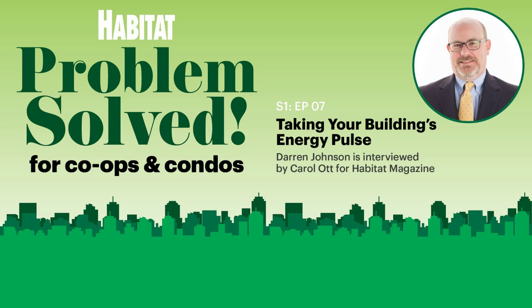If you think about large buildings, you're going to have mechanical ventilation. You may have a cooling tower, a chiller, multiple boilers, much larger pumps and motors. You could have a cogeneration system or a separate domestic hot water system. A BMS is not going to be tied into all of that equipment and all of those systems. It's going to be very specific. What real-time energy management does is leverage that BMS system and then expand upon it. You're creating a bigger network of information that you're monitoring outside of what the BMS is.